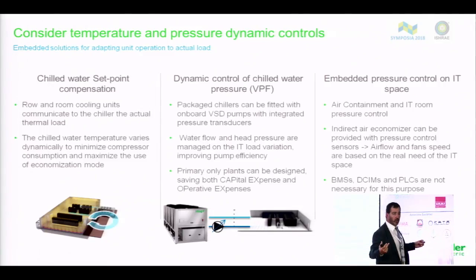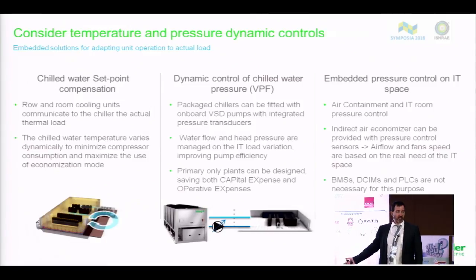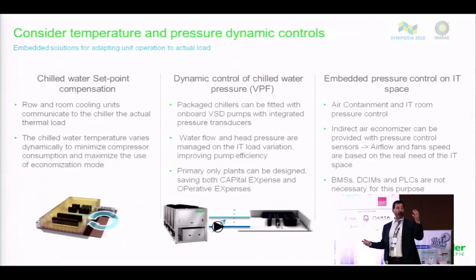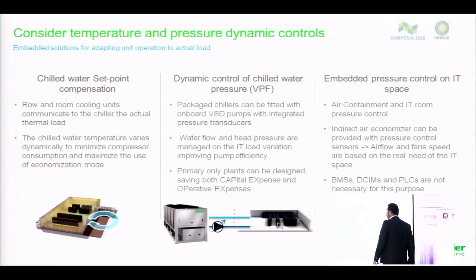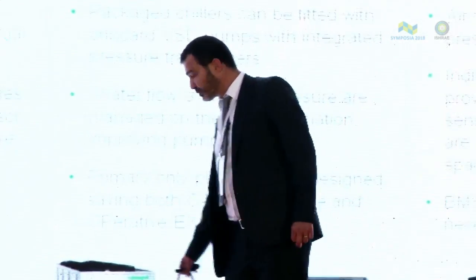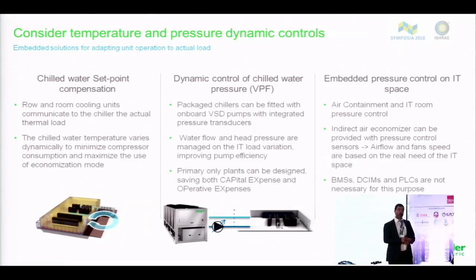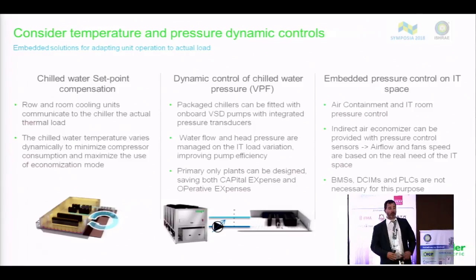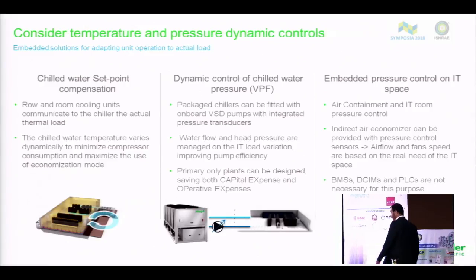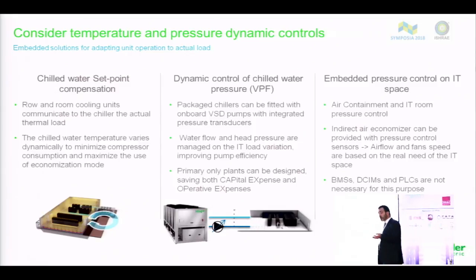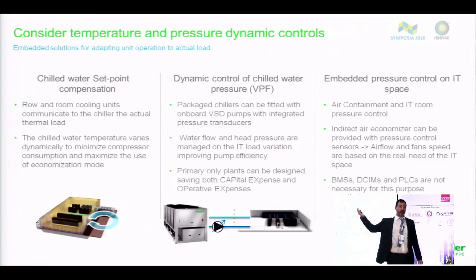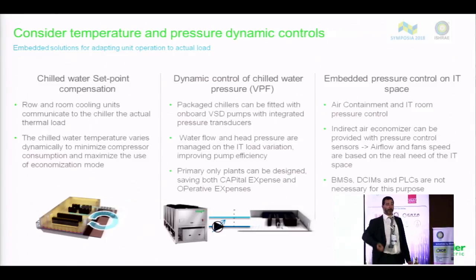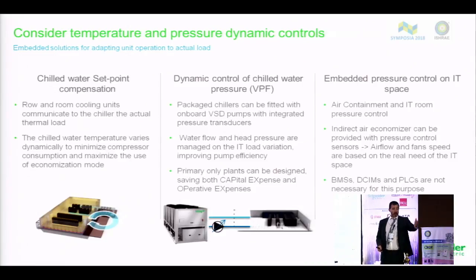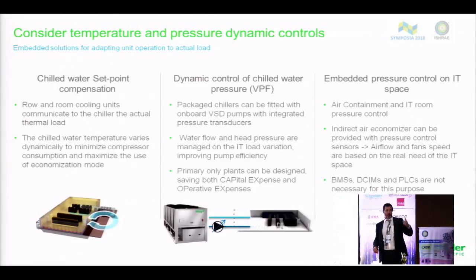This means that at a low load condition, the set point could be optimized. At day one, you don't need the design temperature, you can raise the temperature. Adapt the water flow, so use as much as possible primary circuits with an inverter-driven pump on board the chiller that reduces the water flow to the minimum when it is not necessary to have the full water flow, so at part load condition. There are solutions which allow the pump to be controlled based on a pressure transducer, so low load means that the valve is closed, that means the pump is moving at a lower speed. So by designing at a wide delta T, we already reduce the pump power. With the inverter, we reduce the pump power further.